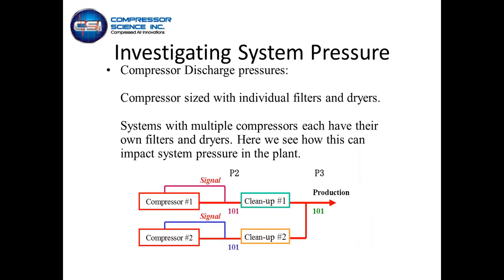The other thing we have to deal with is you have multiple compressors and multiple dryers in a compressor room. Your pressure signal for every compressor, it doesn't matter the control scheme, whether it's load, no load, variable speed drive, variable displacement, reciprocating, you've got a transducer which is integral to the compressor at the discharge of that machine, or a pressure signal which tells that machine what to do, whether to load, whether to back off on the variable speed drive motor, or whether to change the displacement of the rotor on a variable displacement.